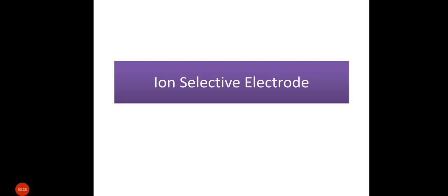The problem of reversibility, considering all electrochemical processes as equilibrium processes, is the contribution of Nernst. The Nernst equation states that the change in potential is proportional to the change in ion activity in logarithmic units of the system. Ion selective electrode measurement involves the use of two electrodes. One is the working or indicator electrode and the other is the reference electrode, whose potential is fixed irrespective of the solution used. The potential that is proportional to the activity of the sample ions is measured across these two electrodes.